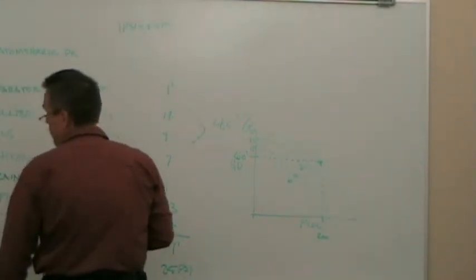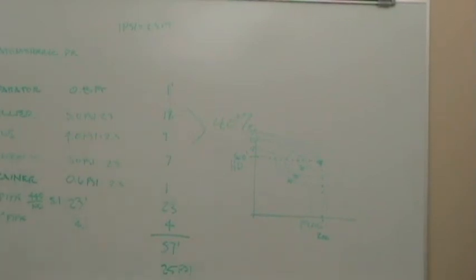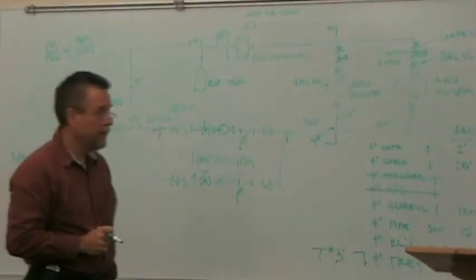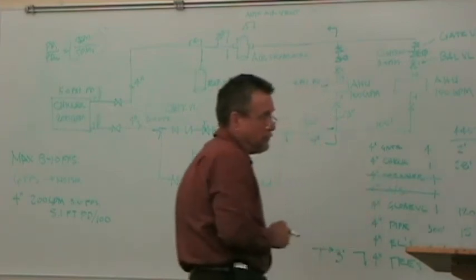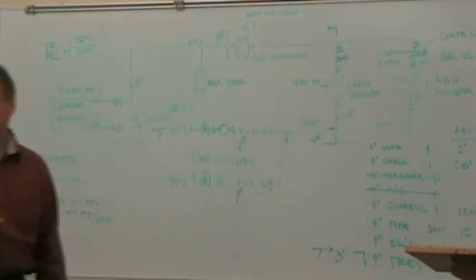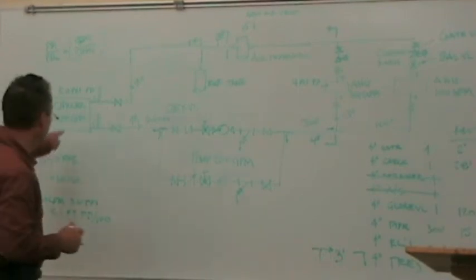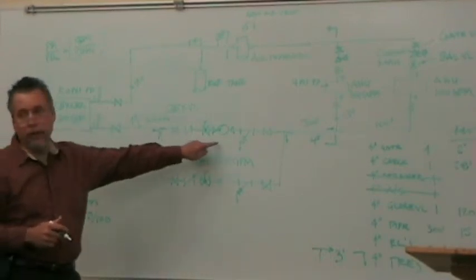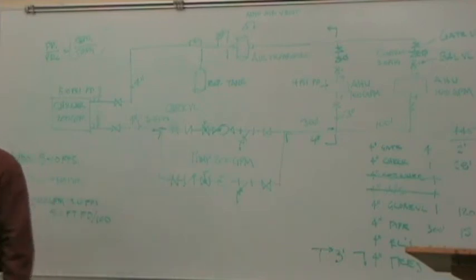So if I had a pump curve, that's probably something like a 2-inch pump. One thing we didn't add in here is probably reducers right here. They'll have some effect on pressure drop, but negligible. So there's my pump. Question: why would you put the reducers in there? Well, for a 200 gallon a minute pump, it's probably a 2-inch or 2.5-inch connection. I've got a 4-inch line. I don't know that for a fact, but I know that a 4-inch pump will probably do 500 or 600 gallons a minute.